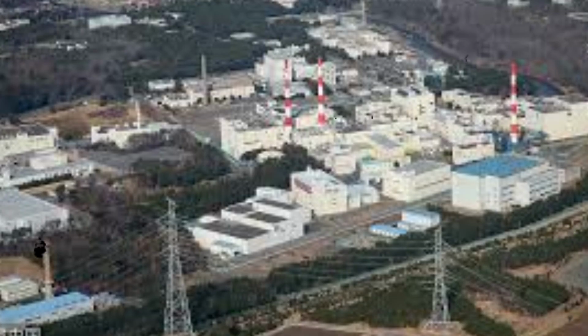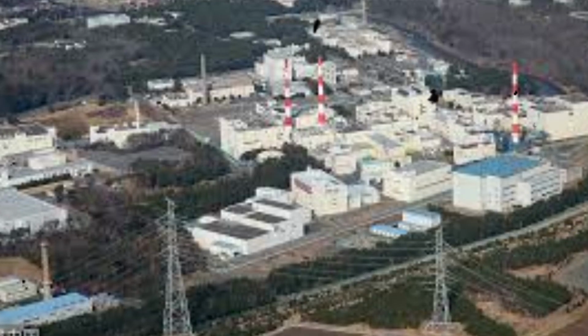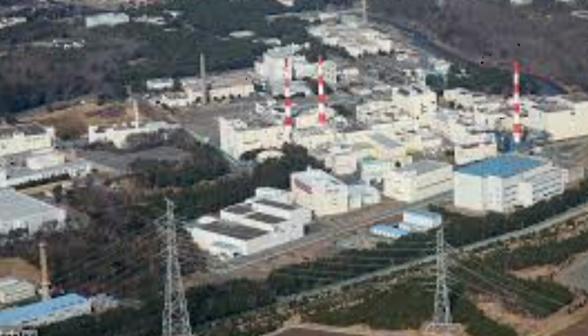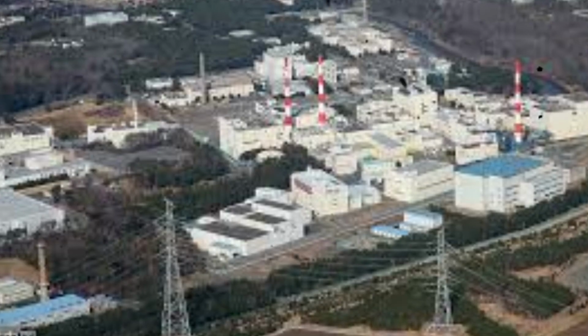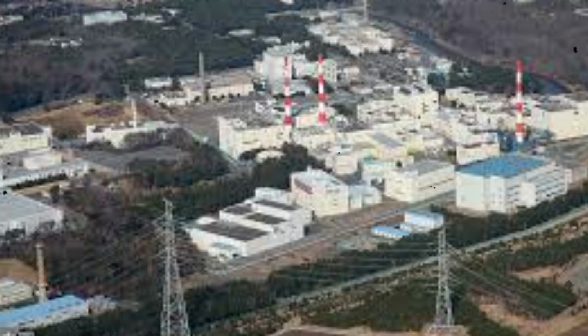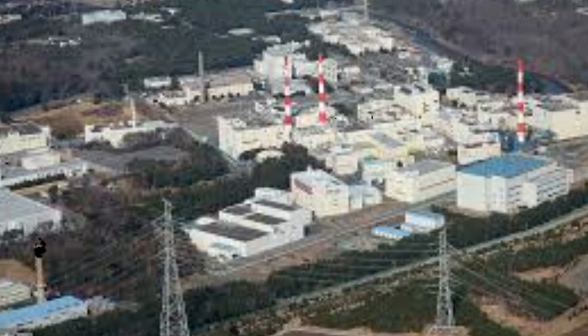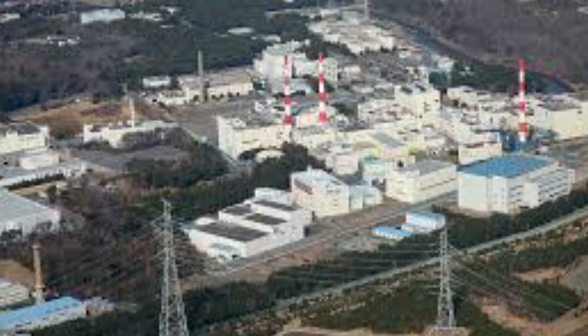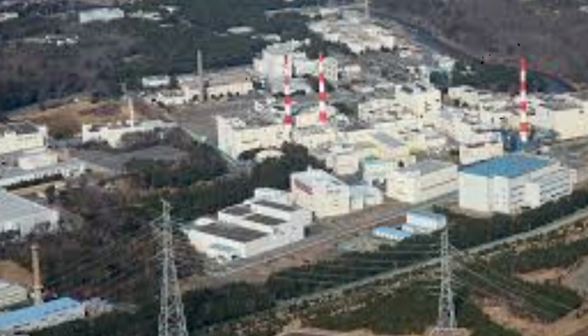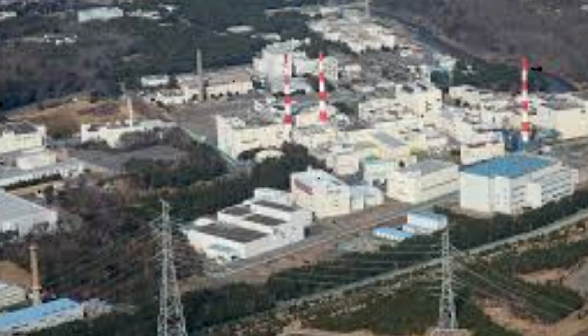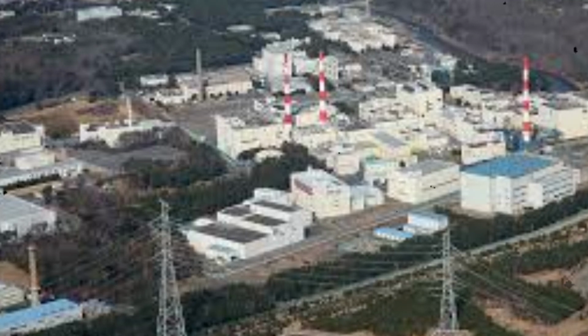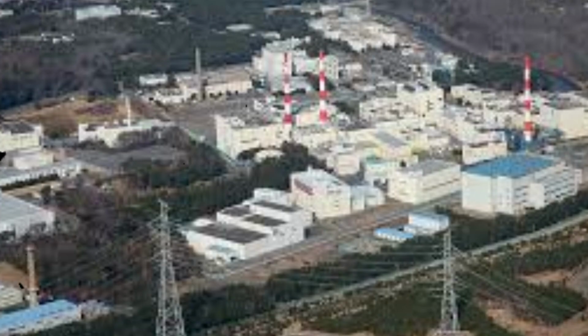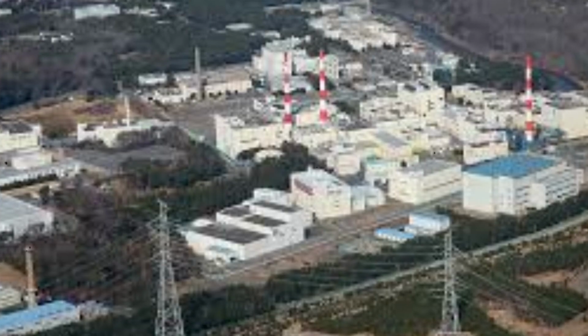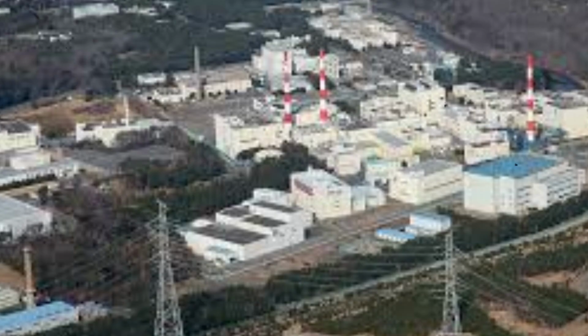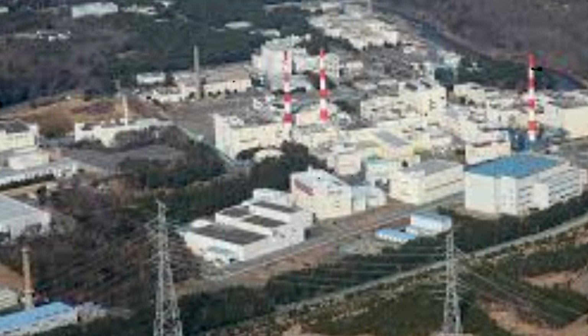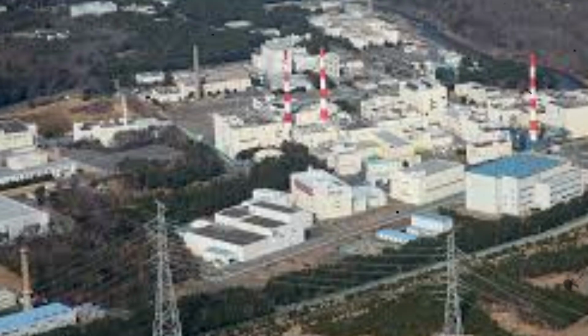The physical progression of tsunami flooding at Fukushima Daiichi followed predictable fluid dynamics principles, but its consequences reflected the fundamental inadequacy of plant design for external flooding protection. Seawater overtopped the plant's seawalls and spread across the site, following topographical gradients toward lower elevations. The emergency diesel generator buildings, designed to protect equipment from seismic forces but not from flooding, were inundated with seawater that penetrated through doors, ventilation openings, and cable penetrations.